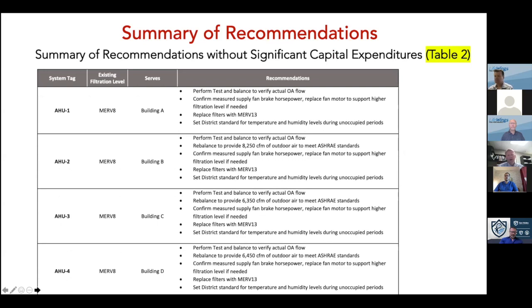So this is table 2, and this one becomes a little bit more complicated because obviously it's tied to capital expenditures. It costs some money to do some of these things, but they're important to do because they make a big difference and they provide solutions to the issues that we're finding. So for example, we won't go through every single air handler because a lot of them are the same, but performing test and balance to verify actual airflows, confirming supply fan brake horsepowers. We've seen a lot of districts across the country just go to MERV 13 filters from MERV 8 filters without checking fan horsepower or static pressures.